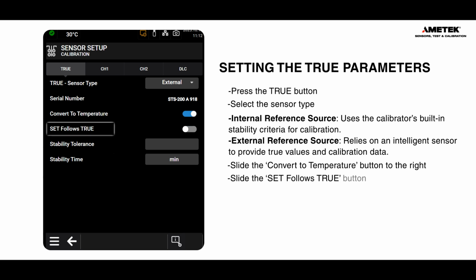The Set Follows True function helps the calibrator match the true temperature measured by the external reference sensor. Simply activate it by sliding the button to the right. When this function is on, the calibrator adjusts to the true temperature, which may take longer to stabilize. This feature is only available when the external reference sensor is displayed in temperature units.